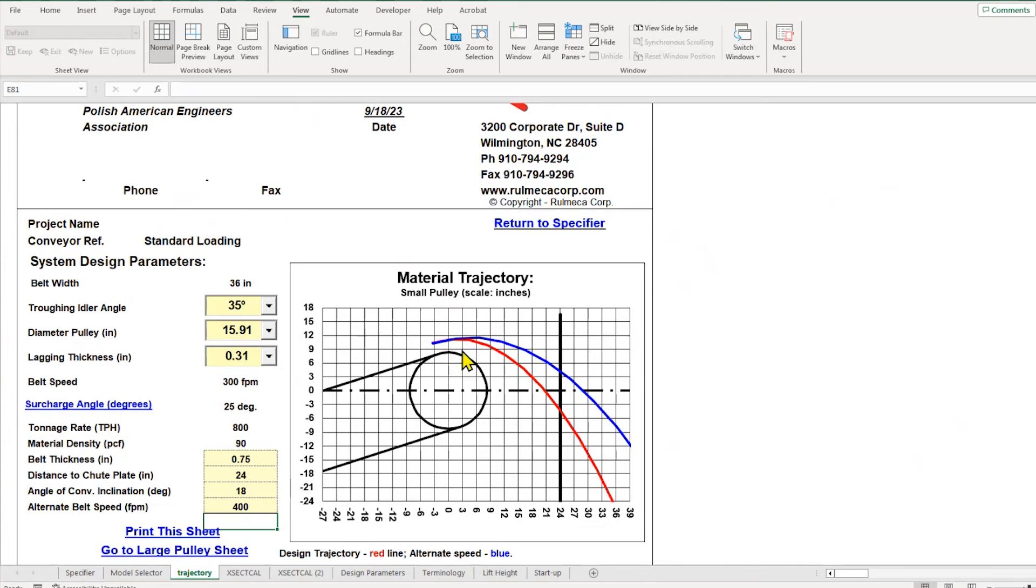We know from experience that if the center of mass of the material impacts a vertical wall above the horizontal center line, this chute will be prone to plugging and not flow very well.